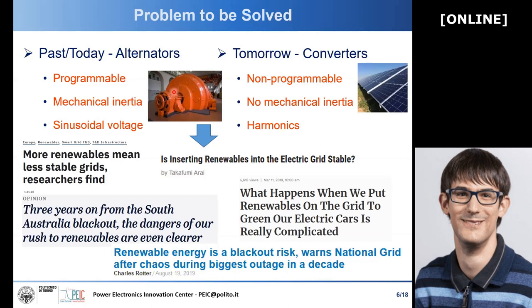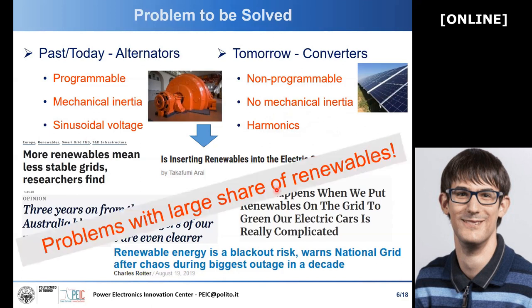Synchronous generators are designed mechanically and electrically to provide a sinusoidal voltage with very high quality. On the other hand, converters and renewable energy systems are not programmable because they depend on the weather as they are controlled today. They don't feature mechanical inertia because there are no moving parts — take the example of solar panels. And since they are interfaced with a power converter, there is harmonic content and harmonic distortion, which can be detrimental for the power grid. This means we risk stability and integration issues, especially when the share of renewables becomes very large.